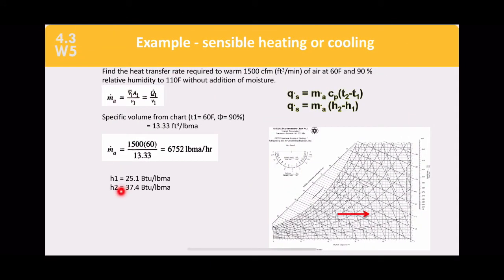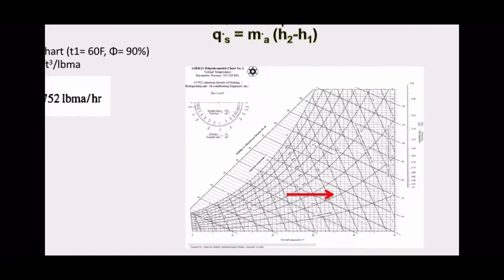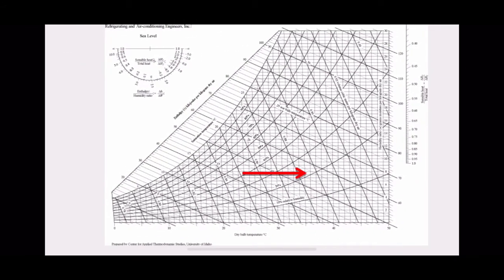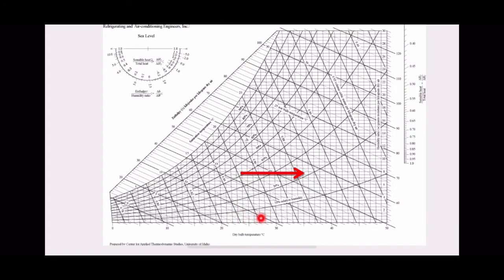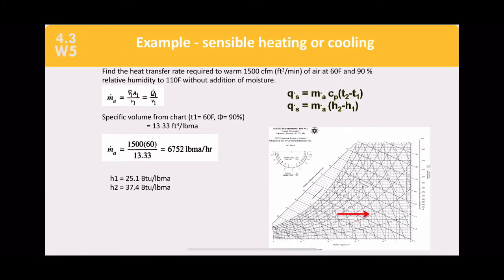h1 and h2 are found from the psychrometric chart using the dry bulb temperatures of State 1 and State 2. Since humidity is the same at both states, the red horizontal line connects both points, making it easy to read enthalpy. Multiply m_a by 60 to convert from per minute to per hour if needed.